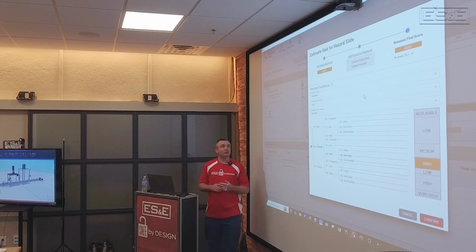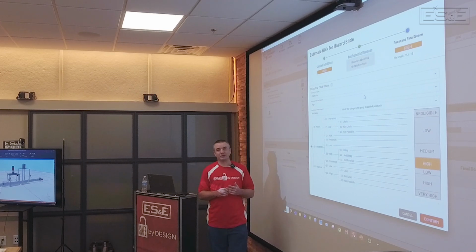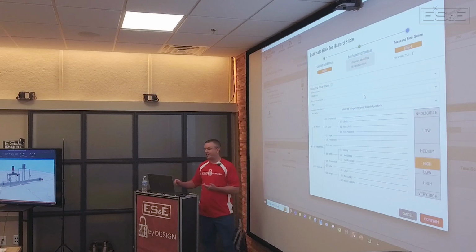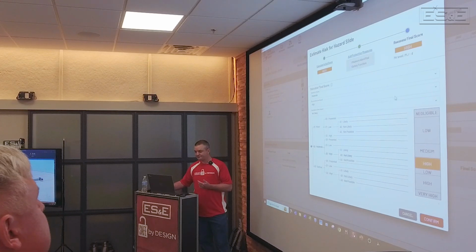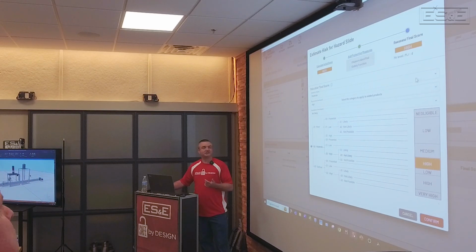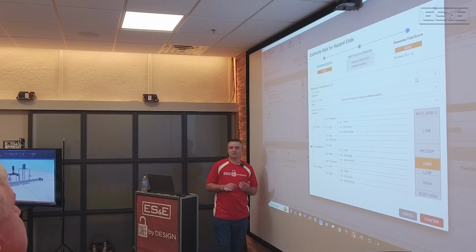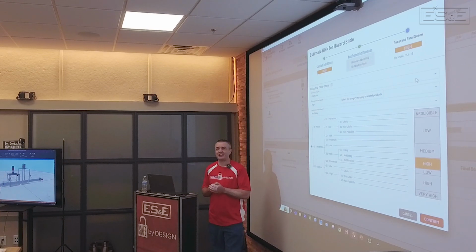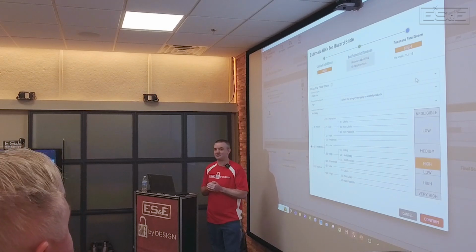So now that we've proposed our light curtain solution for your moving slide or conveyor, let's reevaluate our situation. The severity of the injury is moderate. The operator's still going to encounter that. If he still were to get his hand in there, it's still going to be a moderate hazard. That's not going to change.